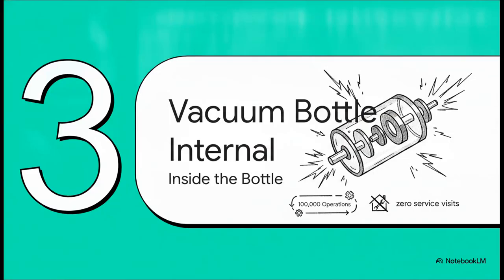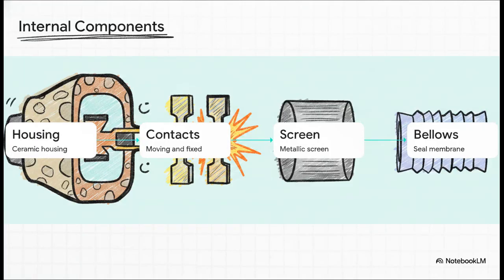Okay, let's shift gears to section 3, inside the vacuum bottle. Let's actually crack open that vacuum interrupter to see how it pulls off 100,000 operations with zero service. Inside every V-contact pole is a sealed bottle made up of 5 core parts. You've got a robust ceramic housing for mechanical strength and insulation. Inside that, there's a moving contact and a fixed contact where the actual electrical connection happens. Surrounding them is a metallic screen. And finally, a seal membrane bellows. This is a genuinely brilliant piece of engineering that allows the moving contact to travel up and down while maintaining a perfect, absolute vacuum inside the bottle.